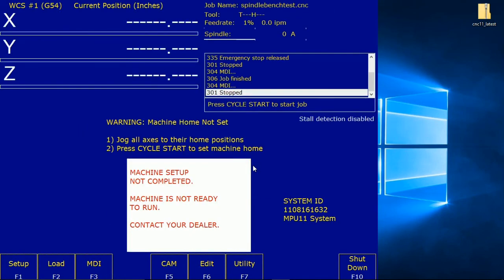Okay, now we're at the all-in-one DC bench test. Bench testing the all-in-one DC will confirm that the all-in-one DC is operational and that the software has been properly configured to begin the installation process. Bench testing is required as it provides a known base configuration that our support engineers can refer to when trying to diagnose any issues that may arise. To complete the bench test, a DVM voltmeter is required.